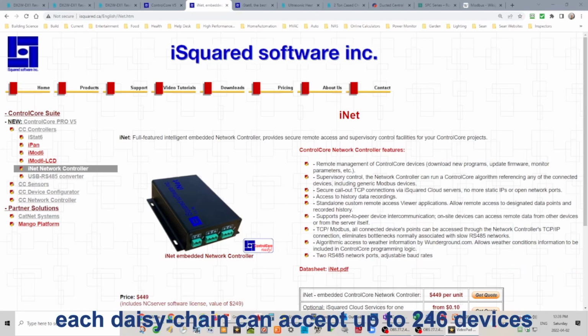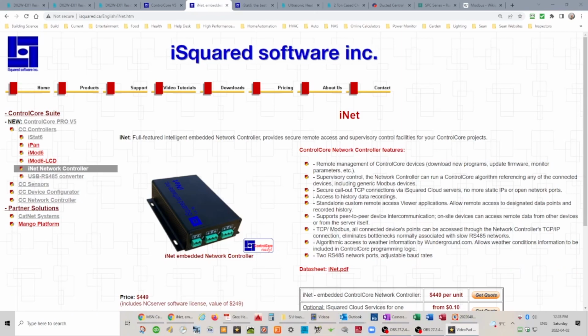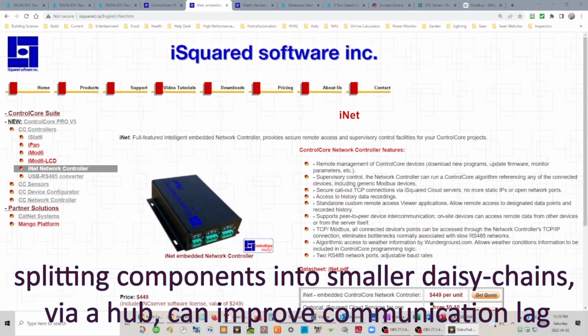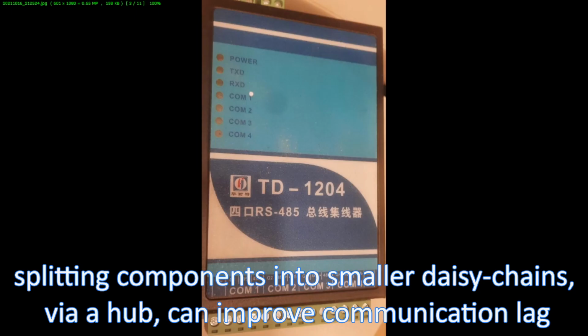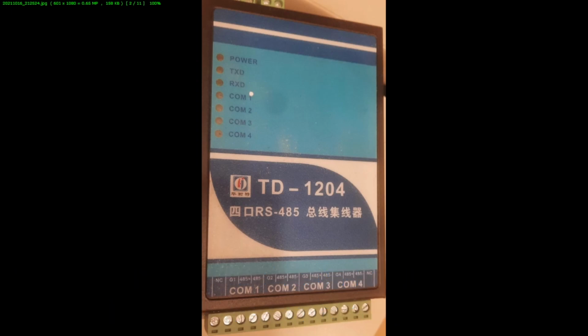If you have more than two daisy chains or two devices, you will then need a hub. And in our case, we are using the TD1204, which is a RS485 protocol hub. It has 4 COM ports. I'm using one of the COM ports for all of the thermostats in the house. I'm using another COM port for the dewpoint sensors that I have on each floor. They're all on one daisy chain.